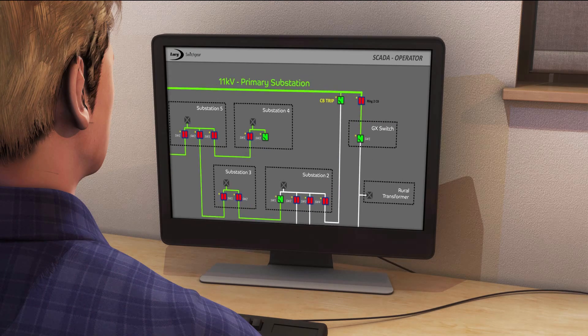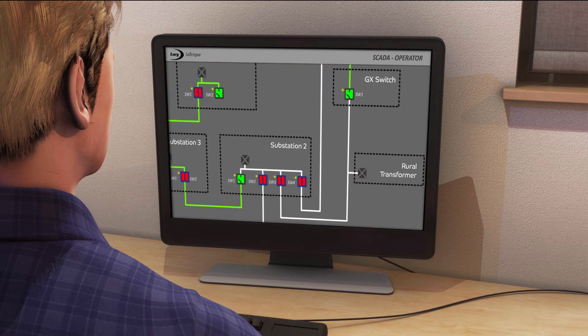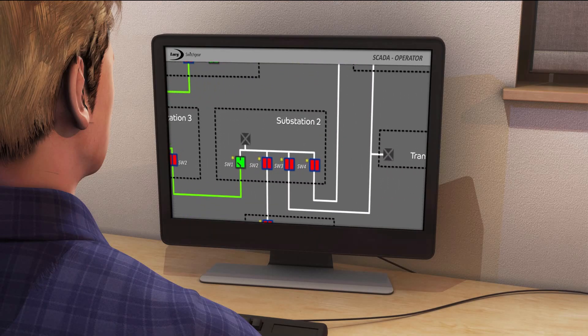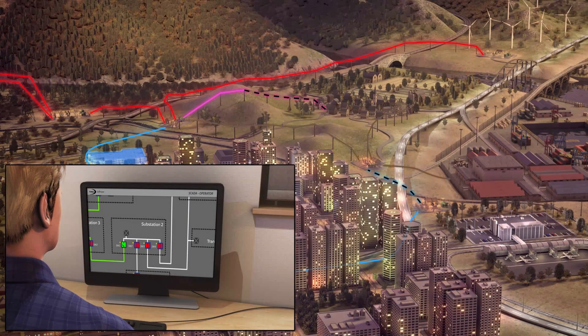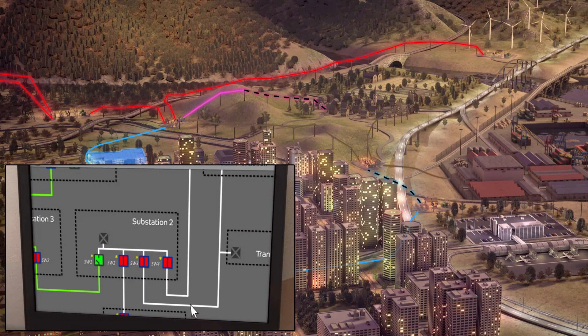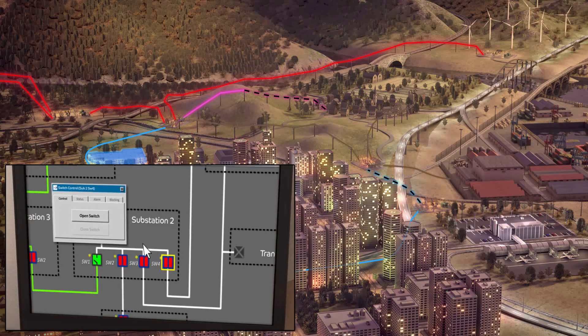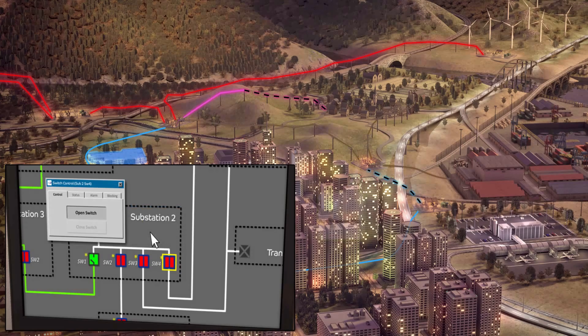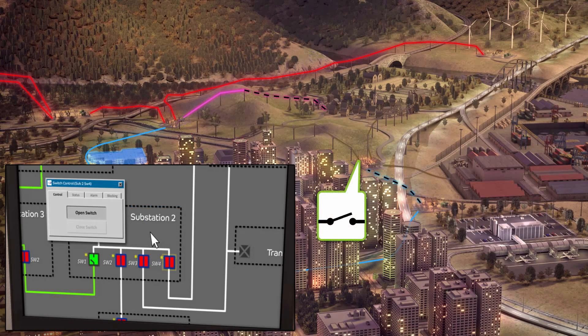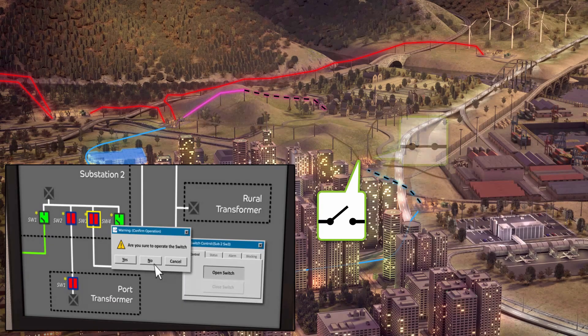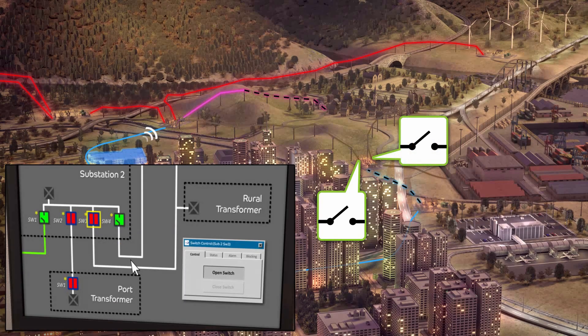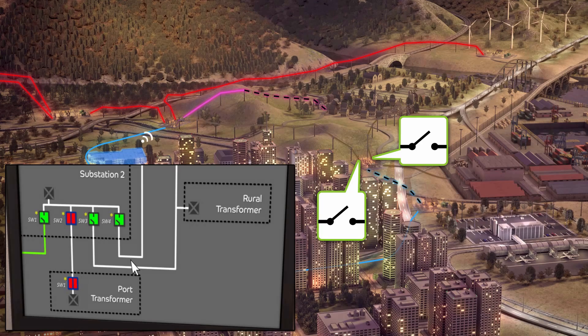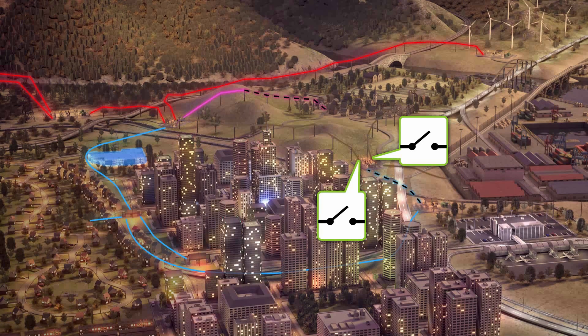The operator can now use the Lucy switchgear SCADA system to isolate this area and re-route power to customers without a supply. The operator remotely opens the incoming switch from the primary substation to substation 2, and then opens the outgoing switch from substation 2 to the rural community. This totally isolates the fault area from the rest of the network.